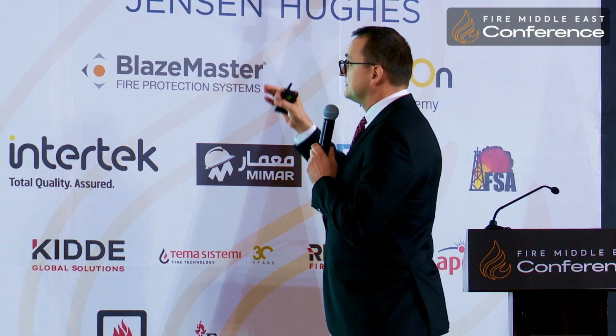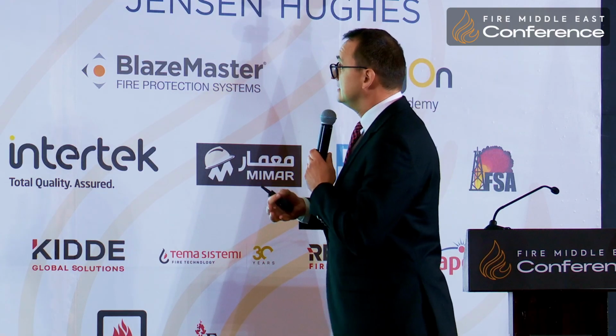manufacturers, there is, I would say, a market practice by the certification bodies: whenever the system does not deliver a rating for all three parameters of stability, integrity, insulation, it is to keep insulation isolated. In our practice, we do the same. Whenever 120 minutes was not achieved because the insulation failed earlier, the insulation time is presented separately. However, I'm asking myself the practical question: if you're planning to utilize that duct system to penetrate a partition wall or a firewall that is rated for 90 minutes, will you be able to use that duct system? To me, no, because even though stability and integrity are ensured, insulation fails after 60 minutes, which means from 60 to 90 there is a risk that fire can spread to another compartment, and the whole idea of compartmentalization is affected.